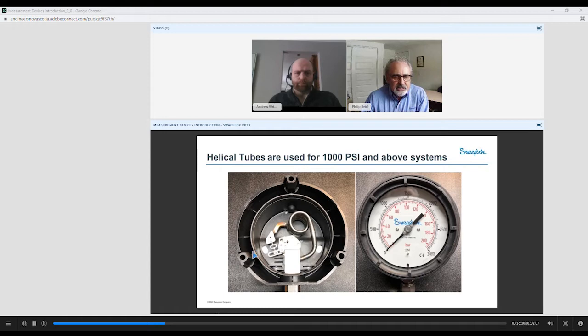Having said that, let's take a look inside a wound Bourdon tube. Looks very similar inside. We have the pressure connection going to the socket, where we have the Bourdon tube welded to the socket, and then it's coiled in the back. It goes to the link, the end piece to the linkage, to the mechanical movement, moving back around to the front. Here we have a dual scale gauge, and we can see this is going to 3,000 psi, so therefore we have the helical wound Bourdon tube. And this is no longer a compound gauge. This is a dual scale gauge, but this will only read positive pressure.